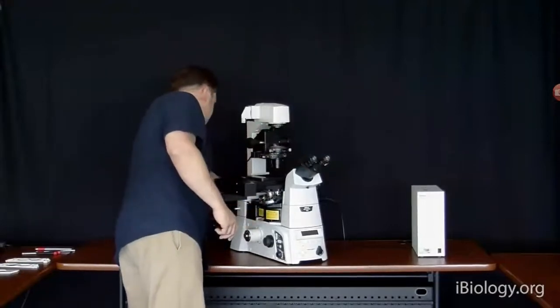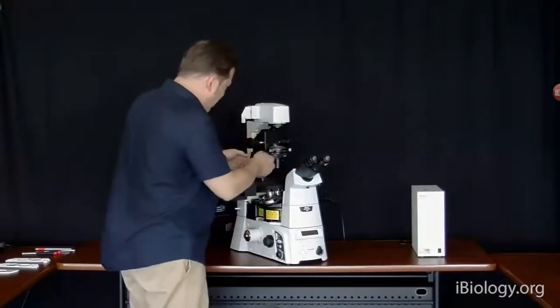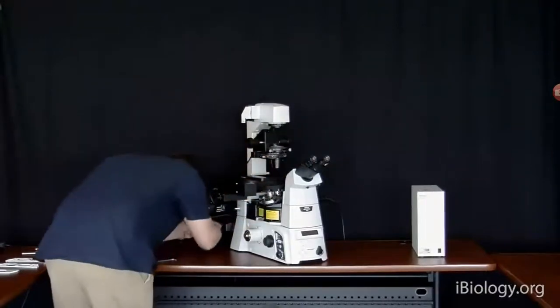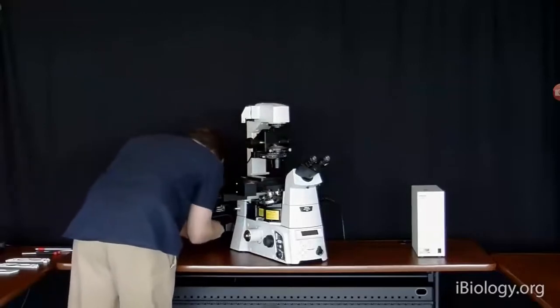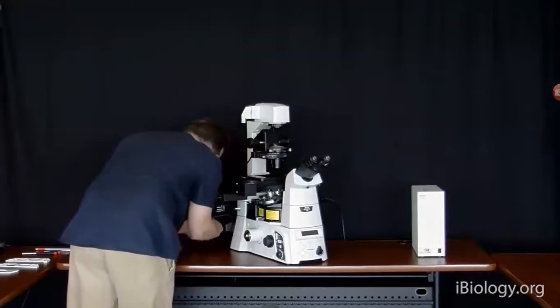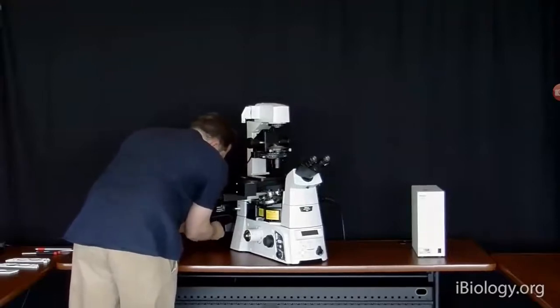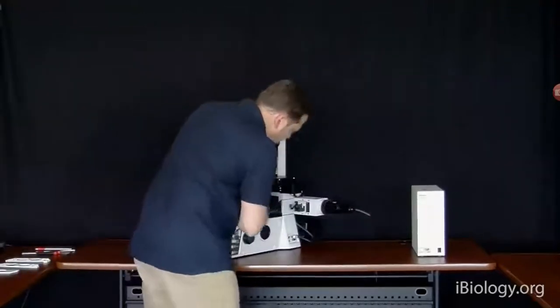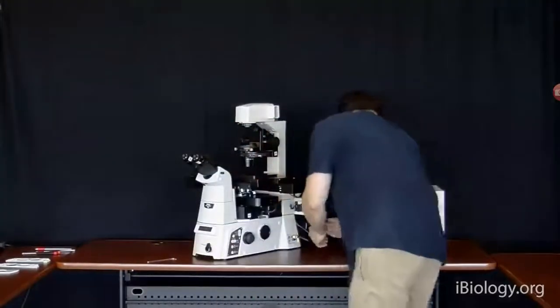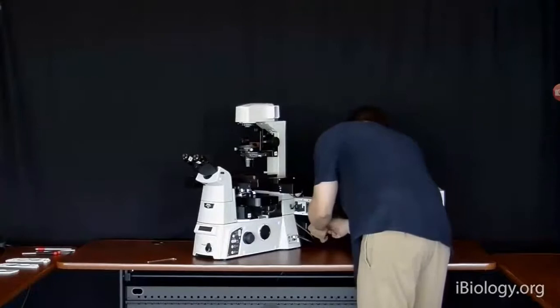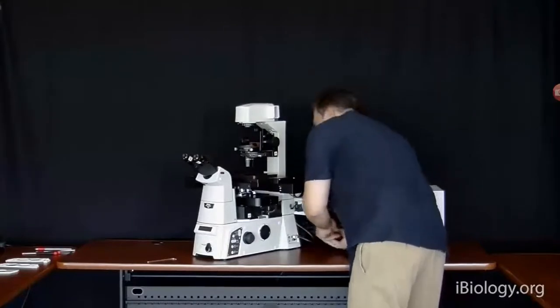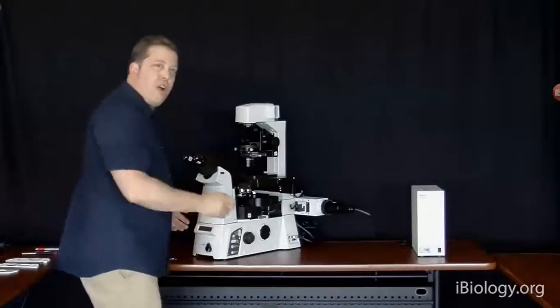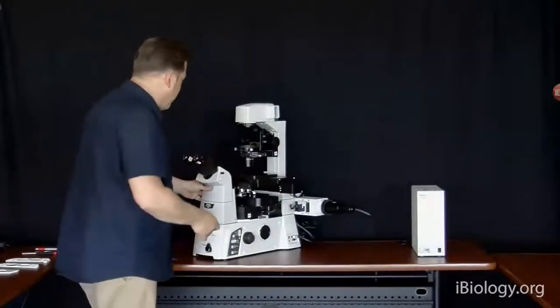Let me also now go down a little bit further. Let me get the covers off the side of the microscope so I can open up the wires, get the wires disconnected. A couple of shields are covering the wiring in the microscope. One on that side and one on this side. Those are going into the hub controller of the microscope, which we'll talk about later.